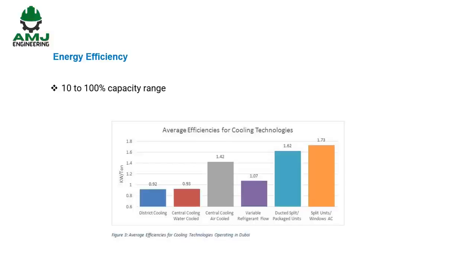In terms of energy efficiency, VRF systems use variable speed compressors with inverter technology with a 10 to 100% capacity range that provides unmatched flexibility for zoning to save energy. Field testing has indicated that this technology can reduce the energy consumption by as much as 30 to 40% a year compared to package or split systems. Here is a graph showing the annual average efficiencies for each of the HVAC technologies for a study made in Dubai by the Regulatory and Supervisory Bureau for Electricity and Water.